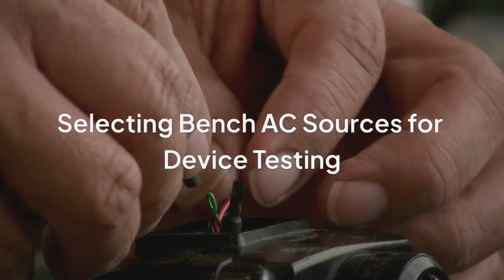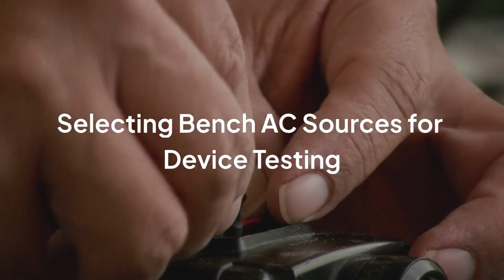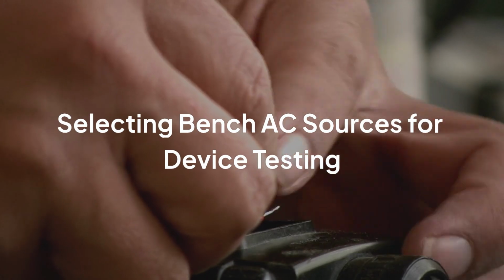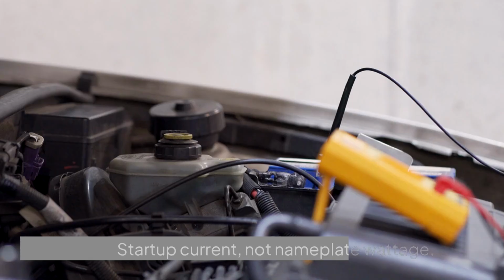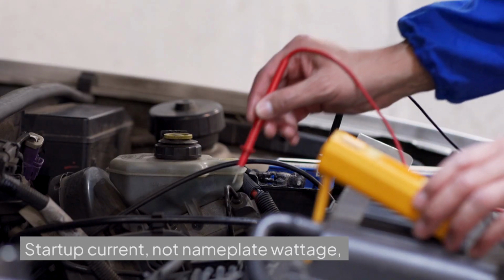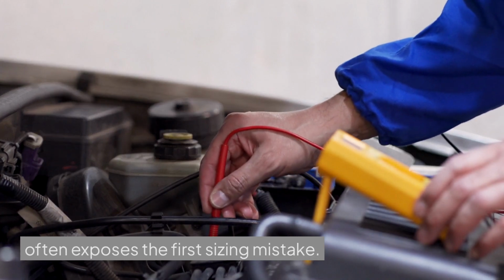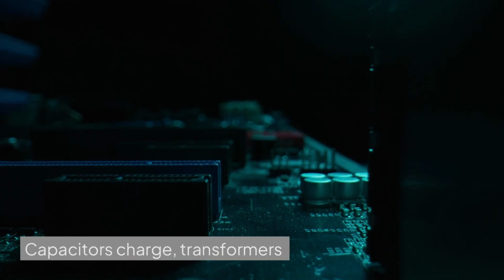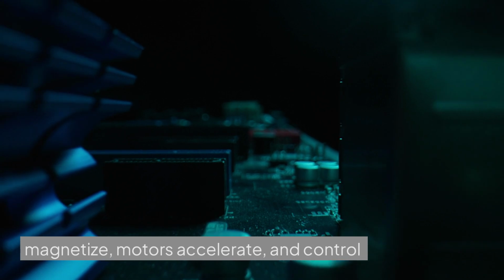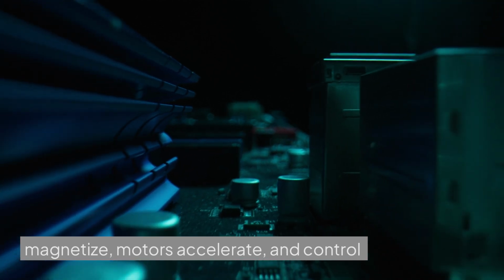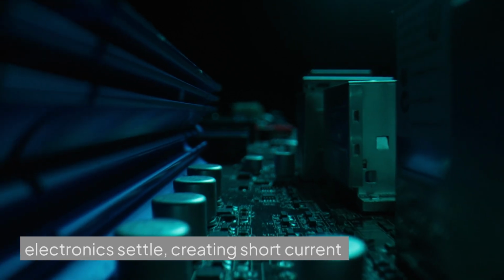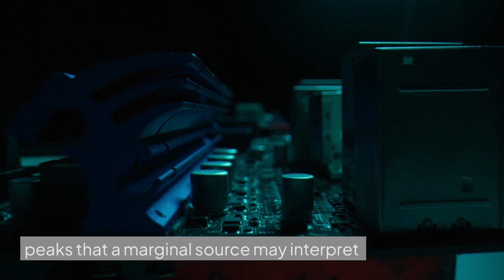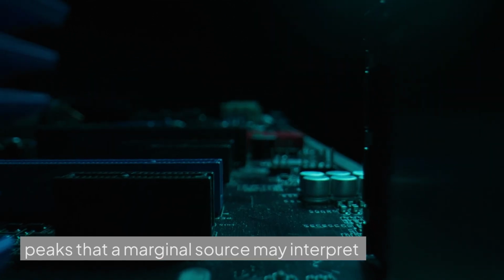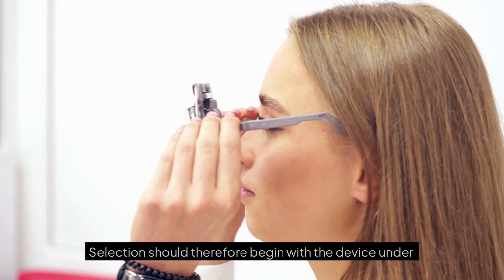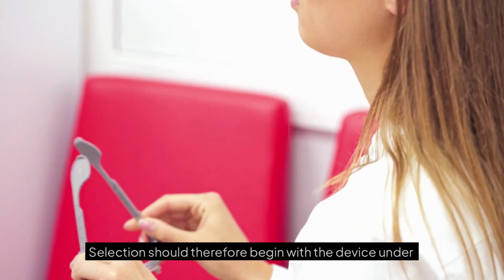A bench AC source can support a device perfectly at steady state and still shut down the moment that device is energized. Startup current, not nameplate wattage, often exposes the first sizing mistake. Capacitors charge, transformers magnetize, motors accelerate, and control electronics settle, creating short current peaks that a marginal source may interpret as a fault. Selection should therefore begin with the device under test.